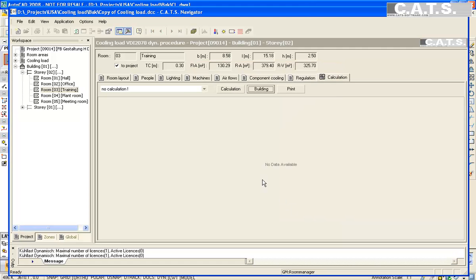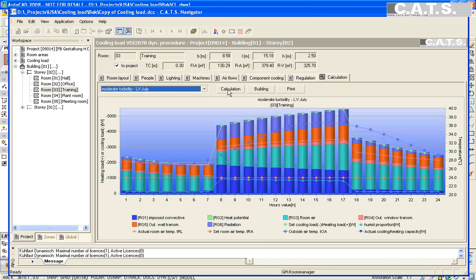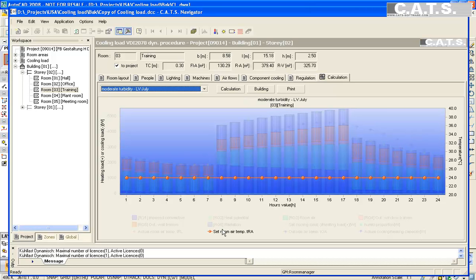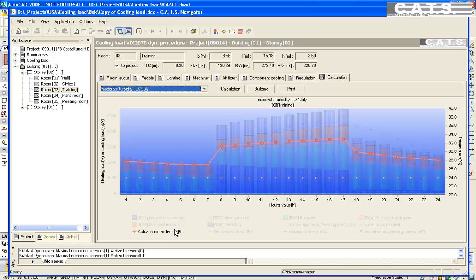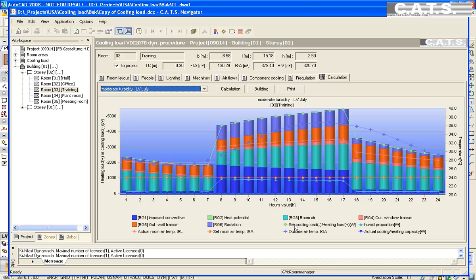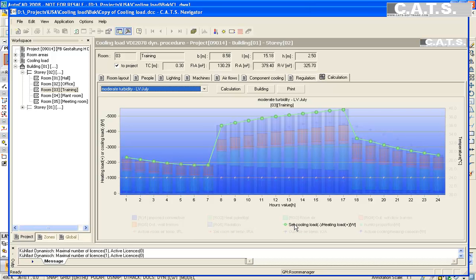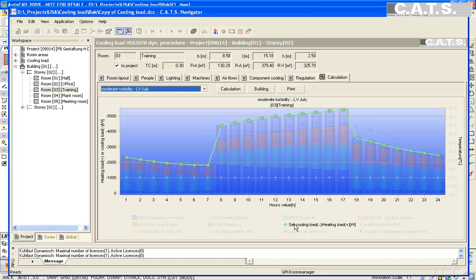Now select the calculation tab and the graph appears simulating our training center. We see the room setpoint here, 24 degrees Celsius. We now see the actual room temperatures over the period of 24 hours. You can see the temperature rising during the occupied period as we have no cooling. Here we see the cooling load. You will see that the load demand exceeded 5000 watts at its peak.